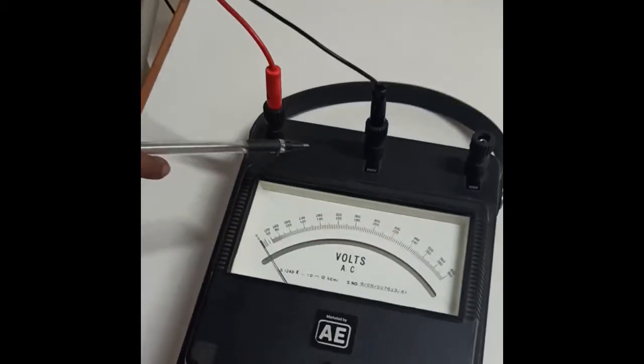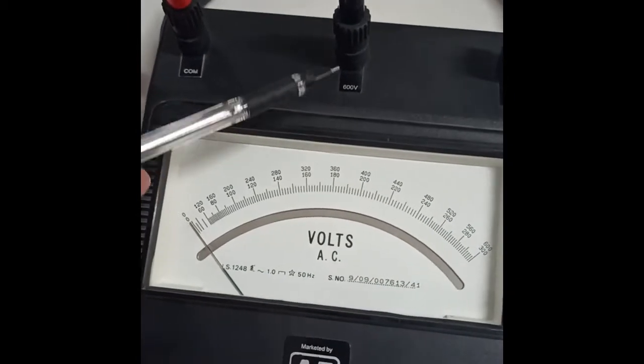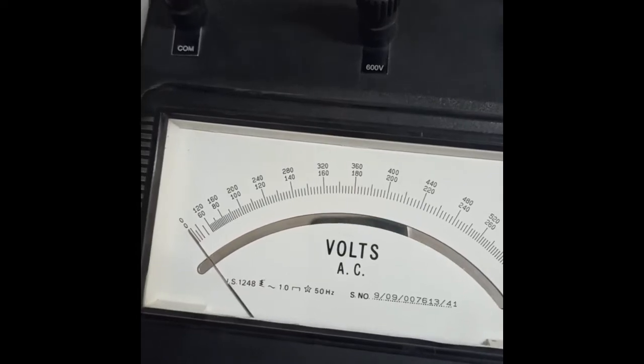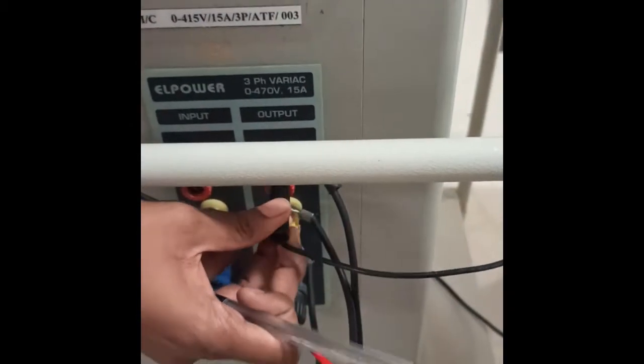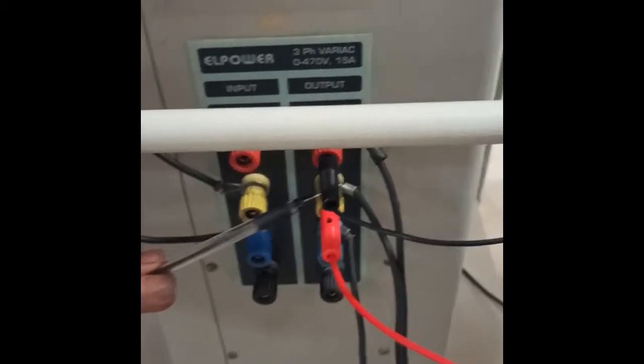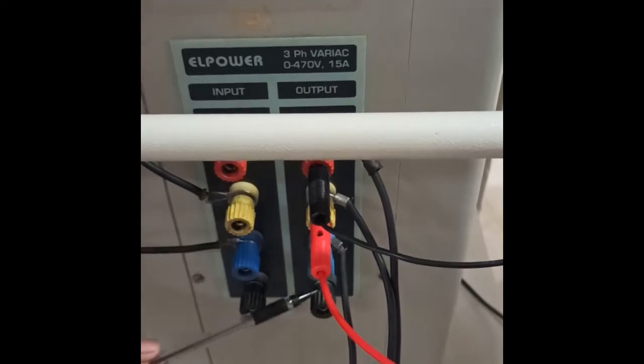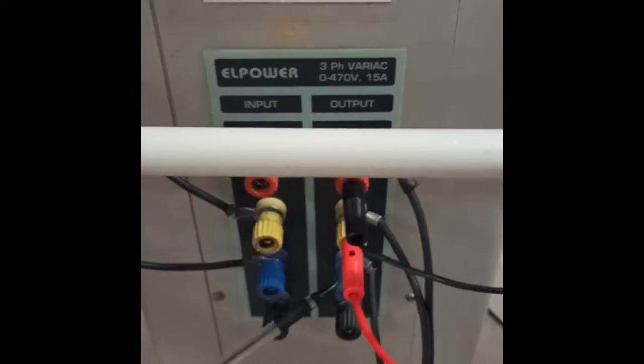The last connection will be the voltmeter. The range of the voltmeter we select should be 0 to 600 volts because it has to measure 3-phase voltage. So that has to be connected to the output terminals of the auto transformer, any two output terminals, either RY, YB or RB. Any two terminals of the output of the auto transformer, the voltmeter has to be connected.